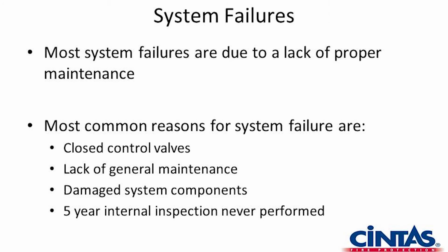System failures. NFPA reports that the main reason systems fail to operate or fail to control a fire when you have an event is failure to properly maintain the system. Most common reasons for system failures: closed control valves, lack of general maintenance, damaged system components, and the fact that 5-year internal inspections aren't performed.